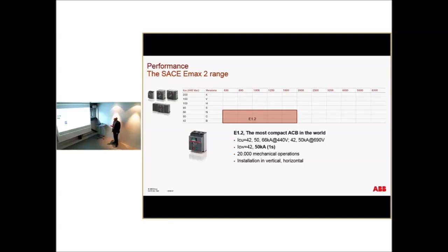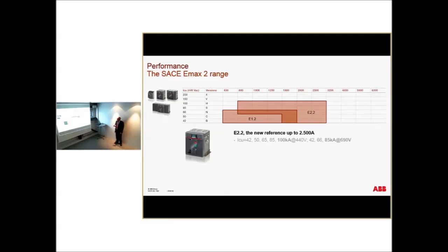Installation can be done in vertical and horizontal position. You see here the width of the switchboard, 300 for a 3-pole and 400 millimeters. The E2, actually, is already a high-performing breaker because it goes up to 100 kA at 440 volts, conditional current, and 85 kA at 690 volts. 85 kA is a maximum withstand current. Again, you see the space here. In the present Emax, you can fit 1600 amps, 2000 amps, sorry. Again, you have 2500 amps in the switchboard IP31.